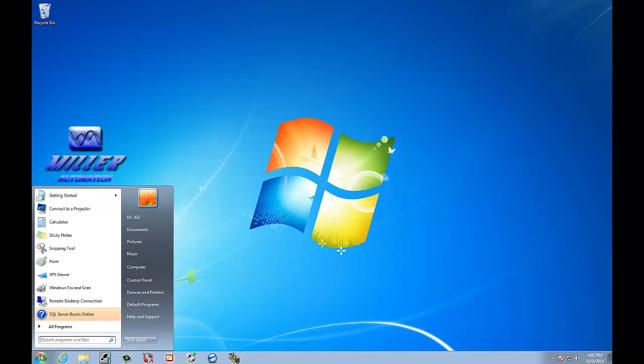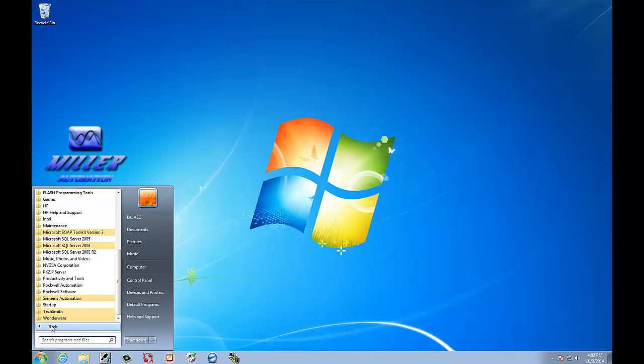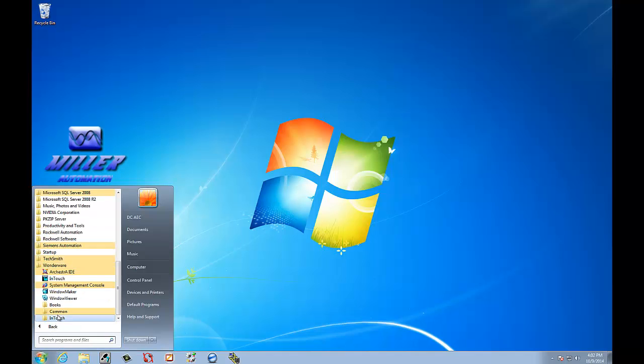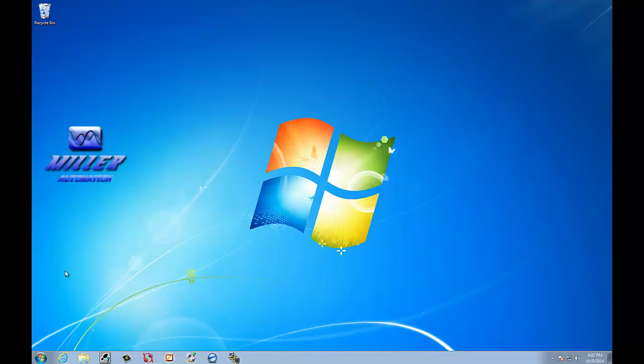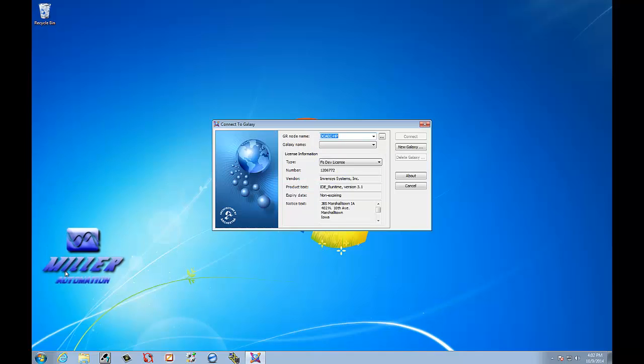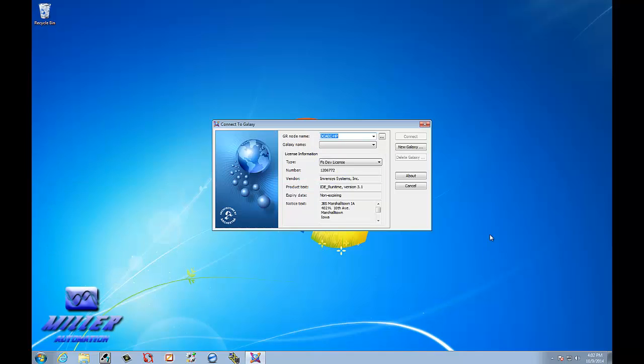Now we can go over and go to Wonderware, and we can launch our ArchestrA IDE. Alright. Now if you set everything up correctly during the SQL Server install, when you go to install the application server, it will automatically set everything up for you and get it going as long as you added your current user and your passwords are the same.